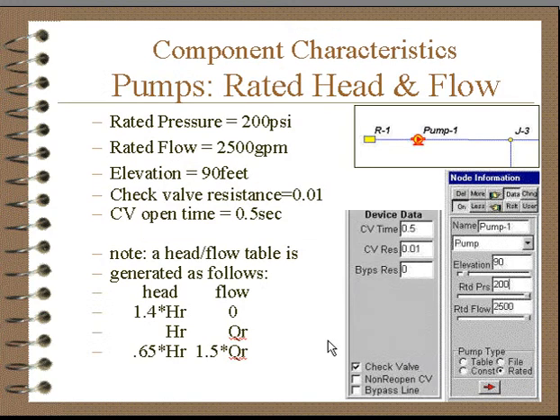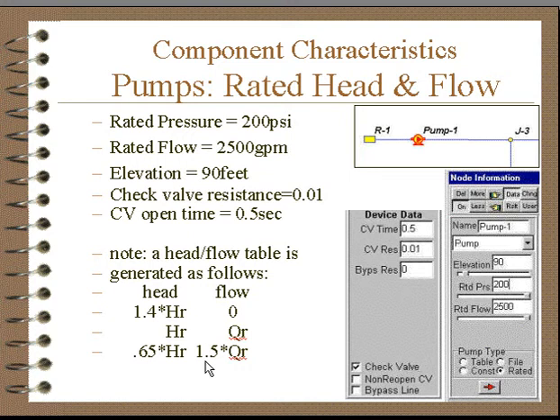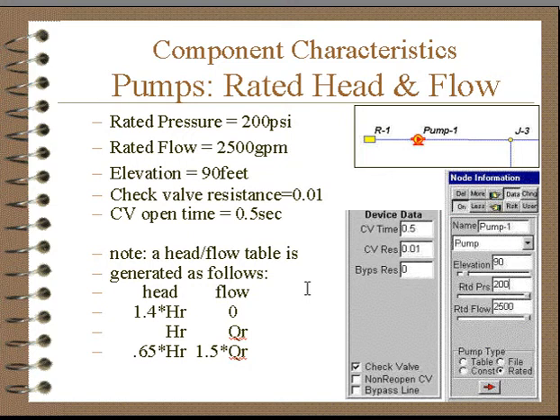If we have a pump described by rated head and flow, internally the program generates an additional point — a cutoff head — and a point at 1.5 times the rated flow, and fits the curve through it. So the same procedure applies to this pump as it does for the head flow table.